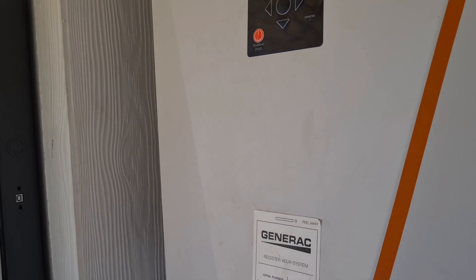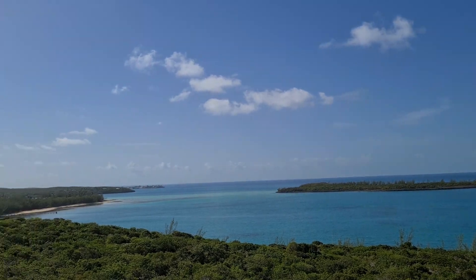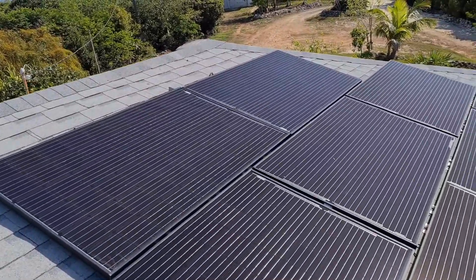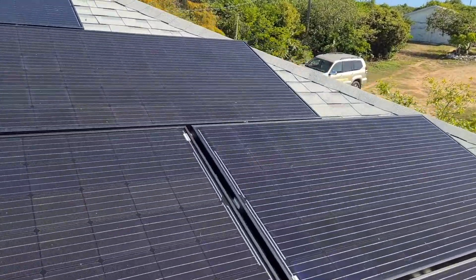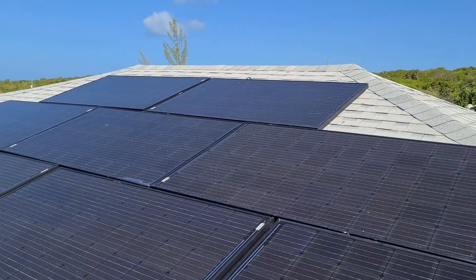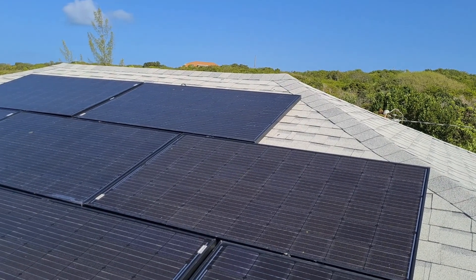Let's go up to the roof — let me show you what we're doing up here. We're on top of the roof, and as you can see it's a beautiful view of Governor's Harbour. This is our solar array. We have monocrystalline solar panels here — they're beautiful, though I personally prefer poly panels. Each one is putting out about 305 watts, roughly 39 volts. We have two strings: String A and String B on optimizers — PV link one and PV link two. Each string can hold up to about 2,500 watts.